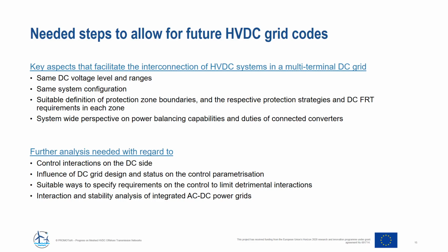So while there are possibilities to bridge that gap while there's no DC grid code, to design a future HVDC grid code and understand how those interactions between the control systems arise, further analysis is needed with regard to those specific control actions, and also the influence of the DC grid design and the status on the control parameterization. So how influential is, for example, taking out one of the lines or turning off a converter to the overall control parameterization and interaction? There are furthermore suitable ways needed to specify requirements on the control to limit those interactions.